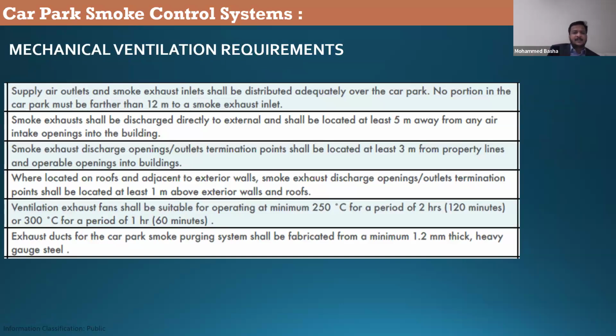There are a few requirements. They're telling you where to place the smoke exhaust outlets. No portion in the car park must be farther than 12 meters from a smoke exhaust, and it should be discharged outside, 5 meters away from any air intake opening. This is normal HVAC, guys. Even for a fresh air design, we do it like this. We will not put the extraction point where we have combustible materials, flames or fumes. You will keep a minimum distance of 5 meters, 3 meters.